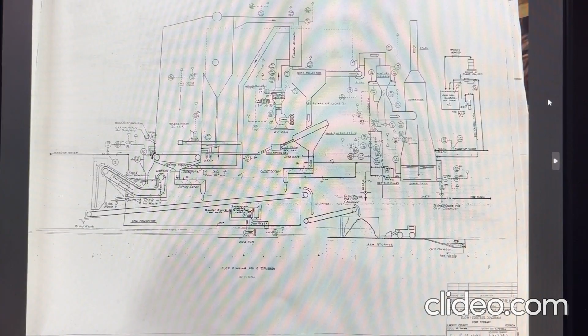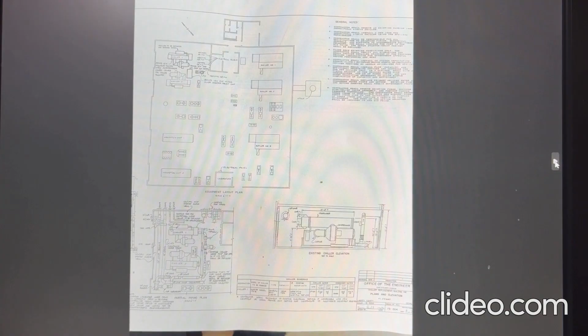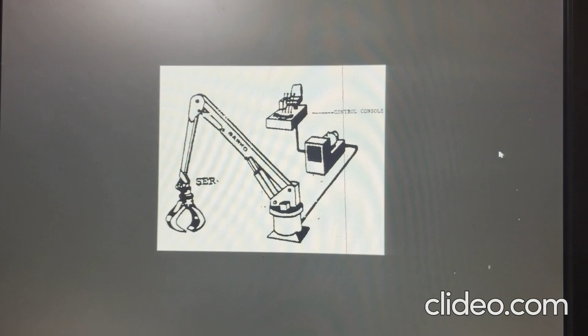This drawing here shows the chillers and boilers inside building 1412. I replaced chillers 1 and 2, which were the 2 regular centrifugal chillers, 1,500 tons each, and there were 2 absorption chillers number 3 and 4, and then there were 3 gas-fired boilers inside the building that I had retubed in various projects. One project I did at the Central Energy Plant for the wood chip hopper was to put in a knuckle boom loader, the mechanical systems and structure to support that. This is kind of a crude drawing of what the concept was to put that knuckle boom loader in with hydraulic cylinder.